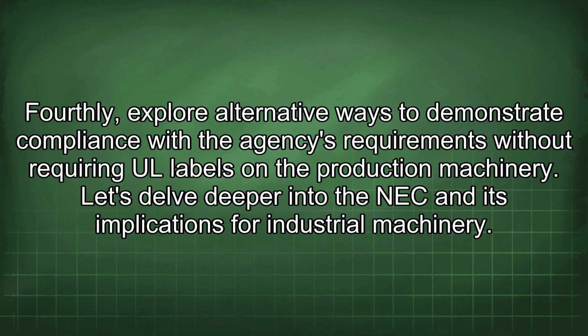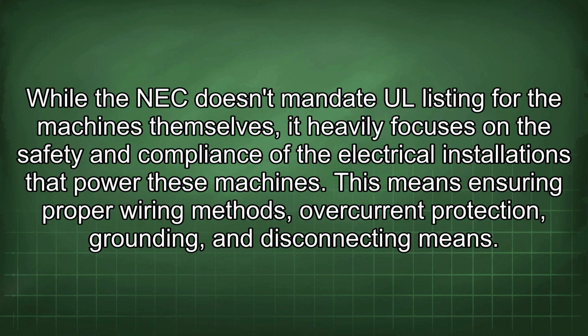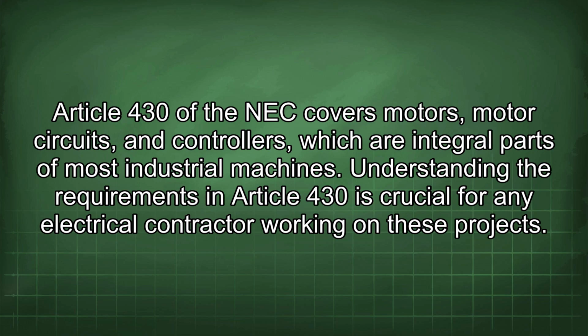Let's delve deeper into the NEC and its implications for industrial machinery. While the NEC doesn't mandate UL listing for the machines themselves, it heavily focuses on the safety and compliance of the electrical installations that power these machines. This means ensuring proper wiring methods, overcurrent protection, grounding, and disconnecting means. Article 430 of the NEC covers motors, motor circuits, and controllers, which are integral parts of most industrial machines. Understanding the requirements in Article 430 is crucial for any electrical contractor working on these projects.